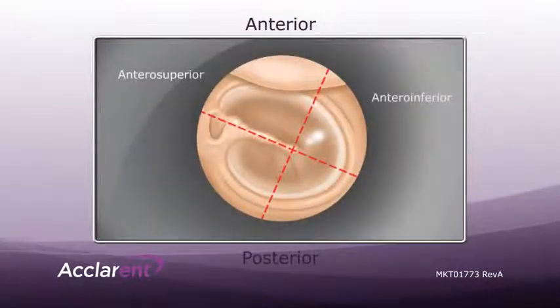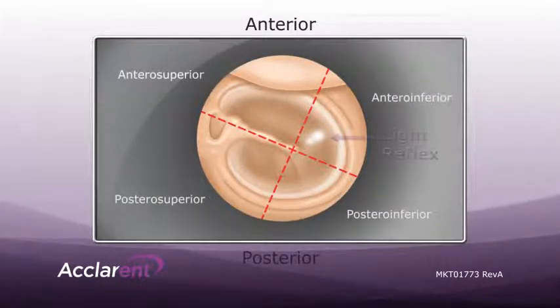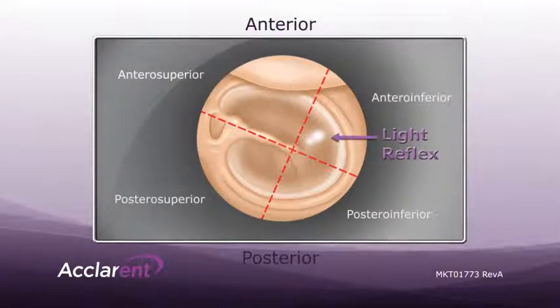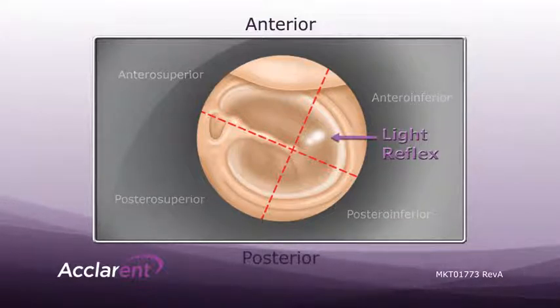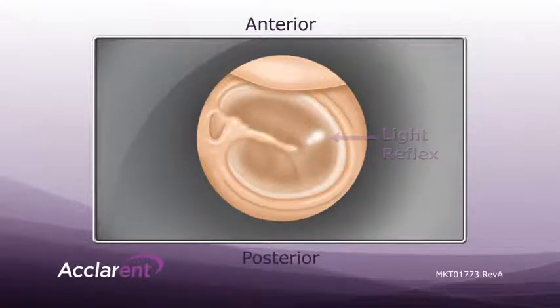During setup, position the patient's head and the microscope such that the light reflex is in the anterior inferior quadrant or other target location. The light reflex indicates that the TM at this location is perpendicular to the microscope.